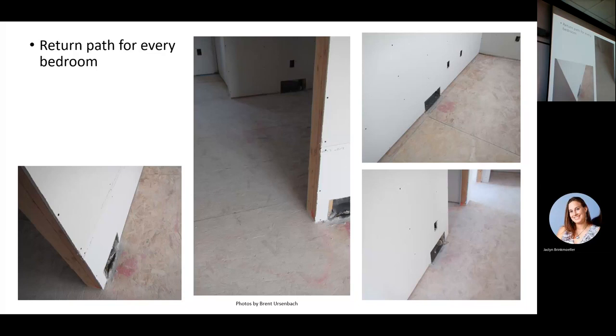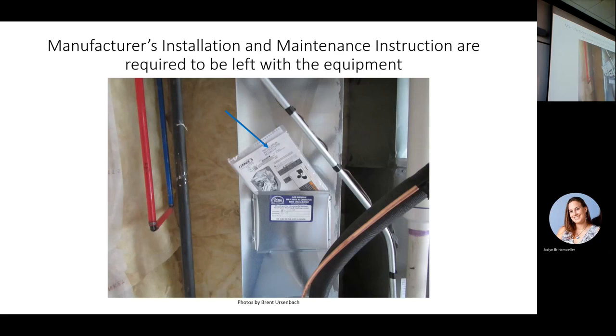Return path from every bedroom. Does it say that in the code? What it says is follow Manual D. And what does Manual D say? Manual D said you have a low resistance path from every supply to a return. So if you don't have a return in bedrooms, you need to have transfer grilles or something to get the air out. You can draw a little bit under a door, but only one 6-inch run can draw under a door if it's undercut an inch and a quarter.